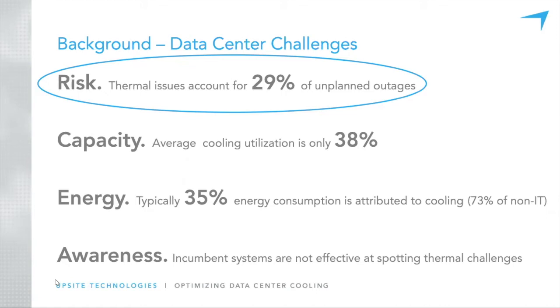Generally, 15% of racks run outside of the ASHRAE guidelines for inlet temperatures, which obviously then leads to downstream thermal issues and outages potentially.